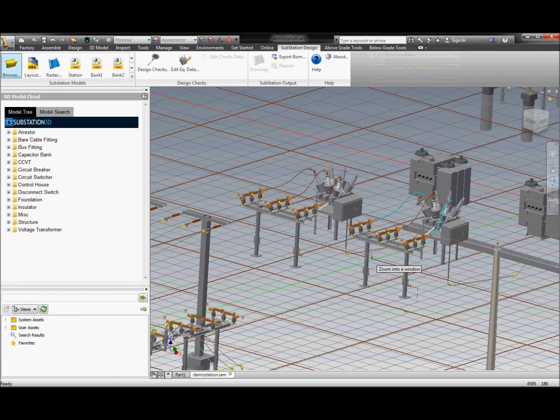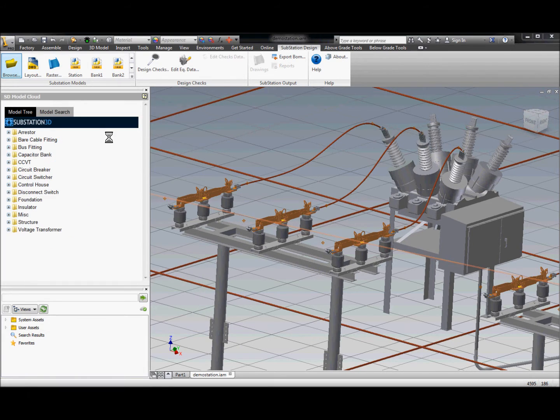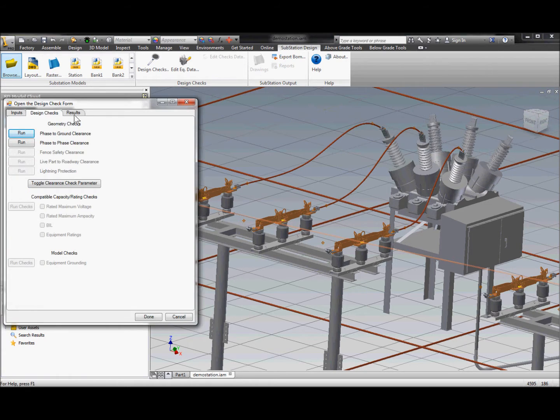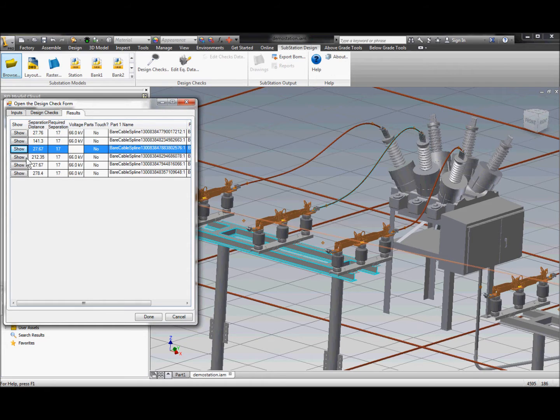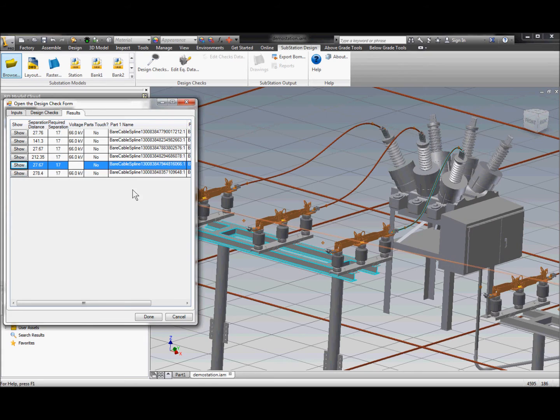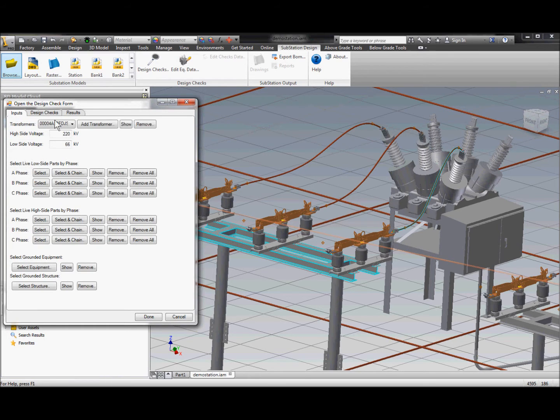Let's orient the model and look at the breaker and some of the insulators to see the intelligence in the library itself. Running a phase-to-ground clearance check — we know what the live cables and fittings are. Keep an eye on that breaker: the insulators will flash on and off. This is using the volumes of the model, removing the features, and doing a true ground clearance check. There are several other checks — you can toggle the clearance checks on and off to remove those volumes and step through each component, as well as review other clearance values.